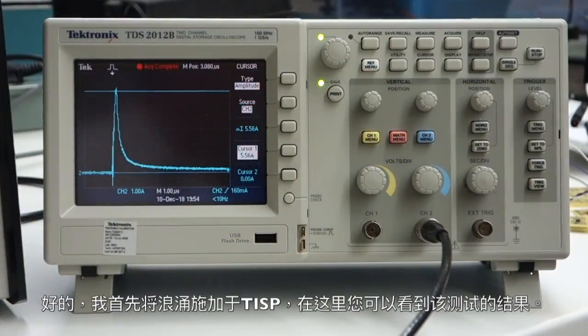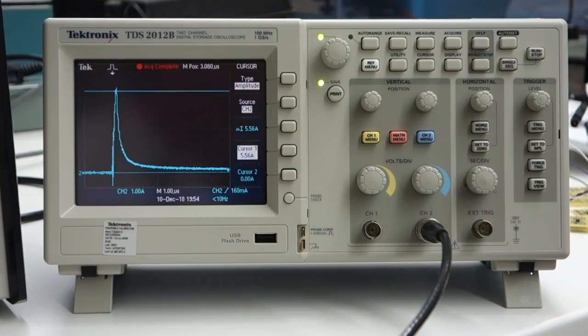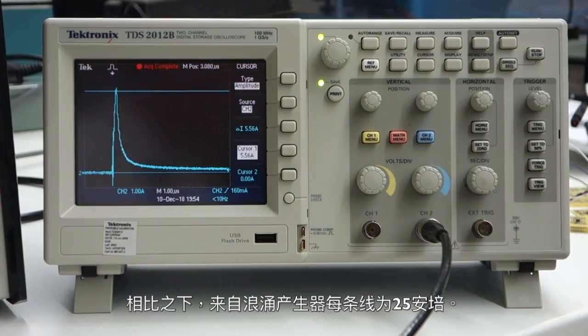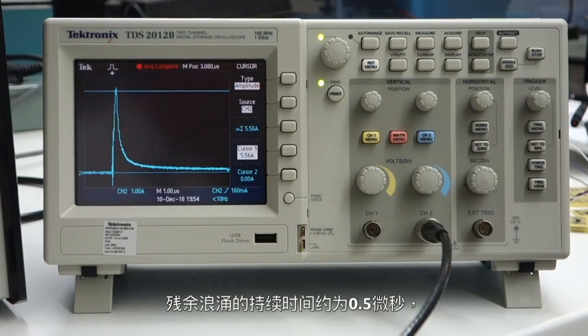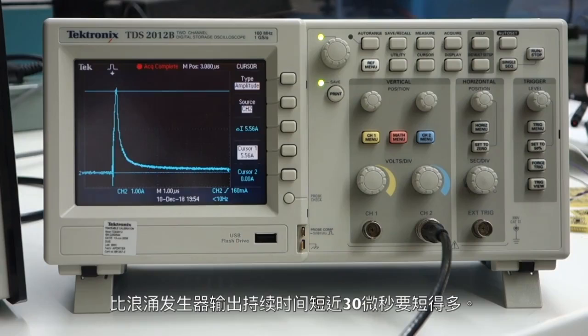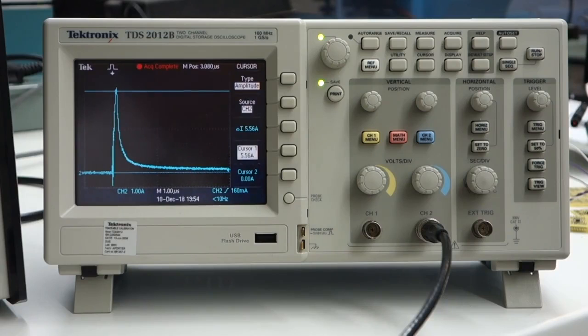Okay, I applied the surge to the TISP protection first, and here you can see the result of that test. The current remaining as a residual during the surge is 5.56 amps peak, and that compares to the 25 amps per wire coming out of the surge generator. The duration of the residual surge is about 0.5 microseconds, which is a lot shorter than the surge generator output duration of almost 30 microseconds.